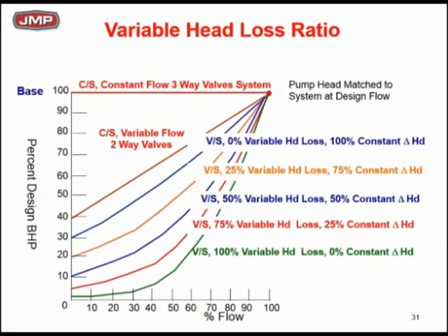Look what happens as I change the ratios a little bit. Let's stay with 50% flow, because 50% flow is going to be the vast majority of the time, half load. Heating load, cooling load, half load, half flow. You're not going to be at 100% flow. Let's look at the real world. Let's look at where we live most of the time. That's going to be around that 50% flow or that 50% load number. Let's go back to my 50.